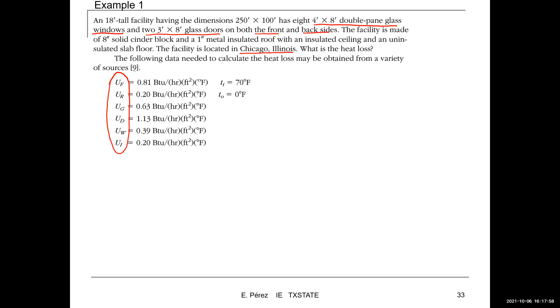This information, location, is important because these parameters are going to be based on the location of the facility. Those are by code, so we're going to bring those in, and those are tabulated as part of the code for the specific state. We also know TI and TO. In this case, we're assuming the temperature inside will be 70 degrees and the outside temperature will be 0 degrees.